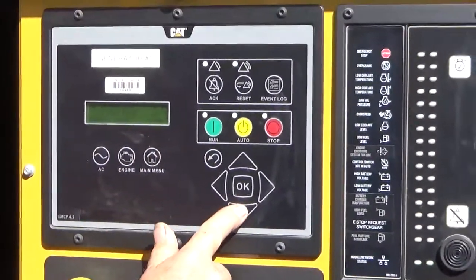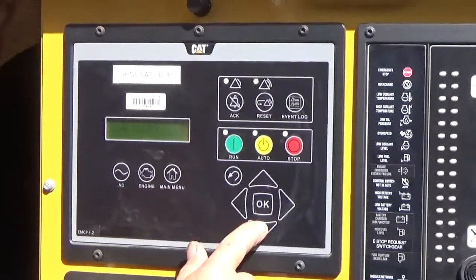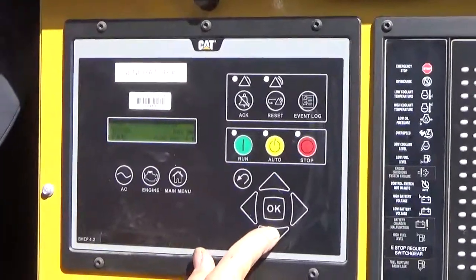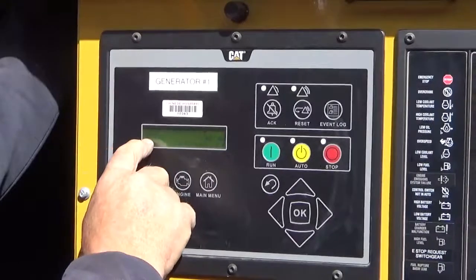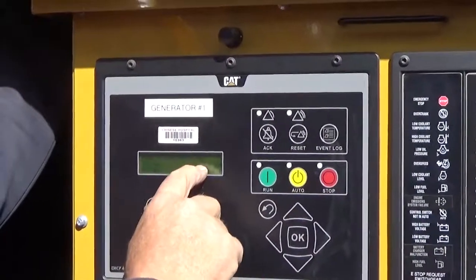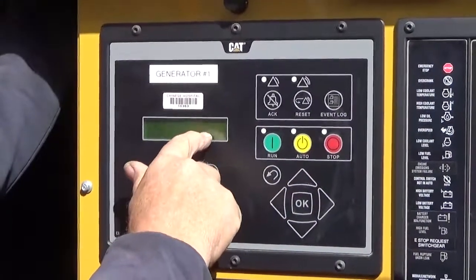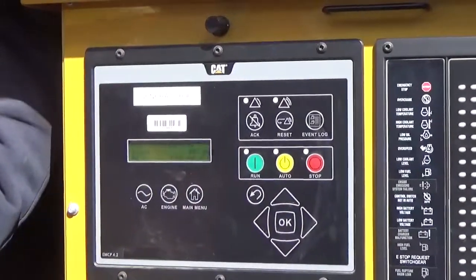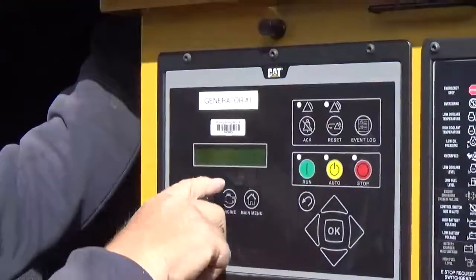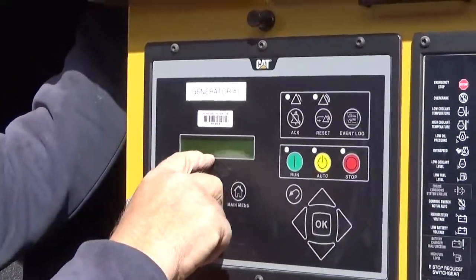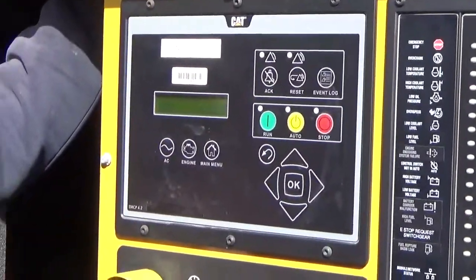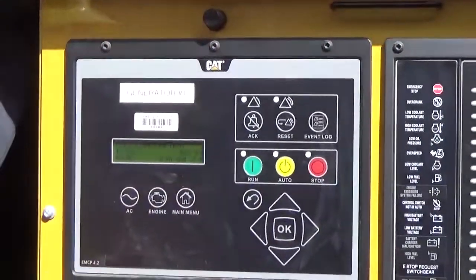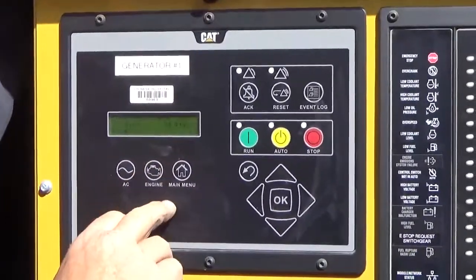So scroll down, and it'll give you total starts. And what's nice is right here, this is the total in its lifetime so far, through all the testing and everything, this thing has burned 887 gallons of fuel total. When it's running, it'll tell you exactly how much fuel it's using when you're online. That's on the engine, you're scrolling through the engine ECM.